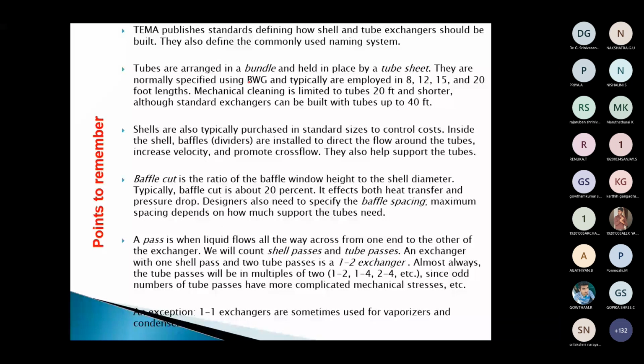Then coming to the pass, a pass is when liquid flows all the way across the exchanger from one end to the other end. Usually we have 1-2 exchangers, 1-4, 2-4, etc. You can see the number of passes on the shell side times 2 gives you the tube side flow: 1 into 2 or 1 into 4, 2 into 2 or 2 into 4, something like that. The tube and shell side arrangements are made accordingly.